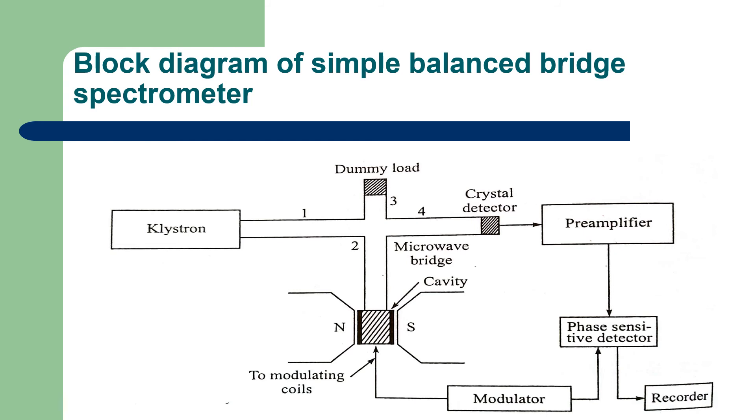Phase sensitive detector is used to detect ESR signal and represented as absorption or first derivative curves. The magnetic field is swept over a small range across the resonance condition by varying the current in a pair of sweep coils mounted on the cavity walls.